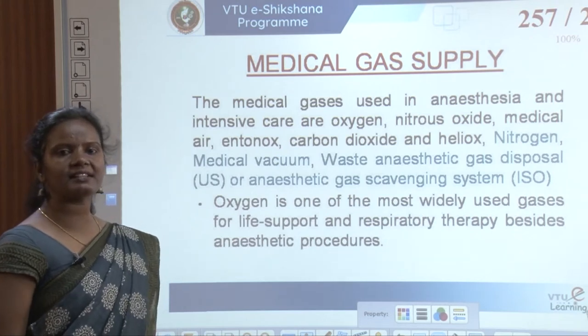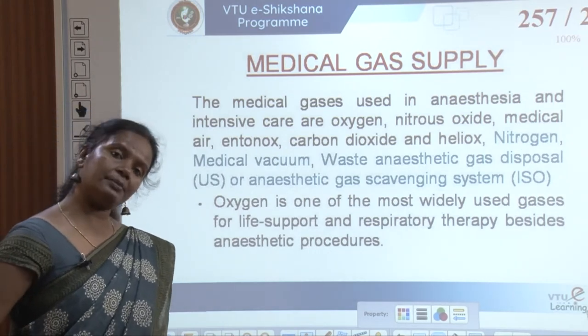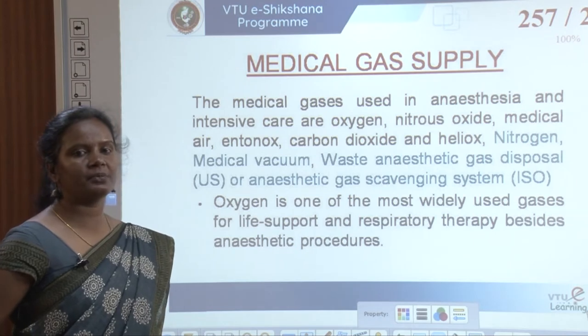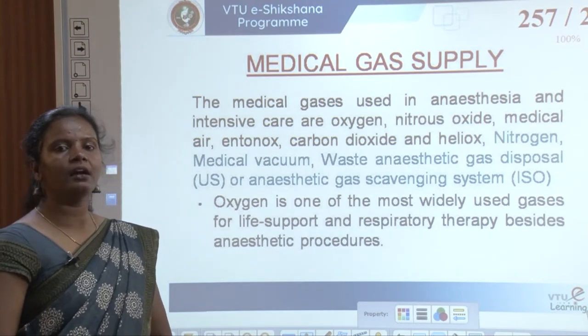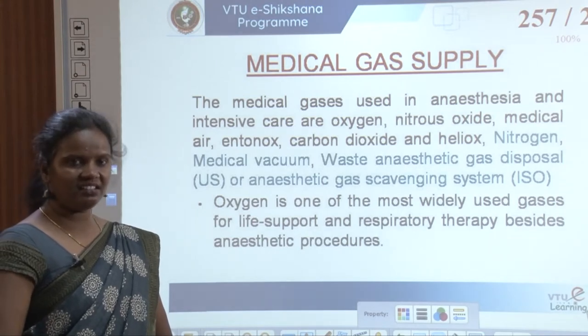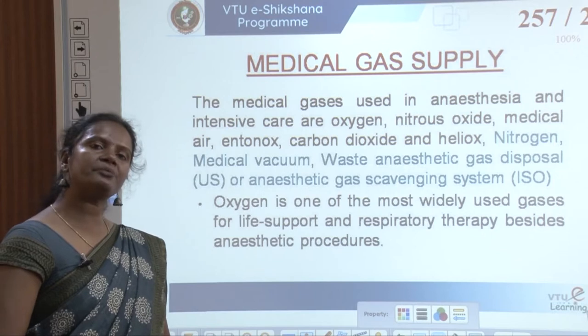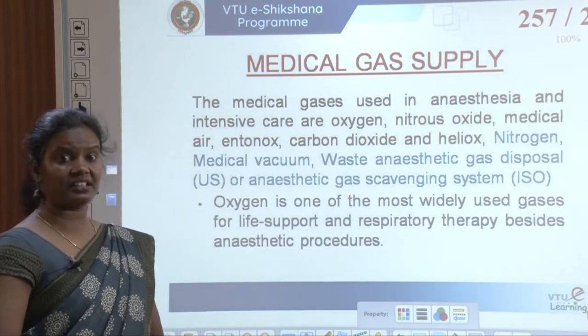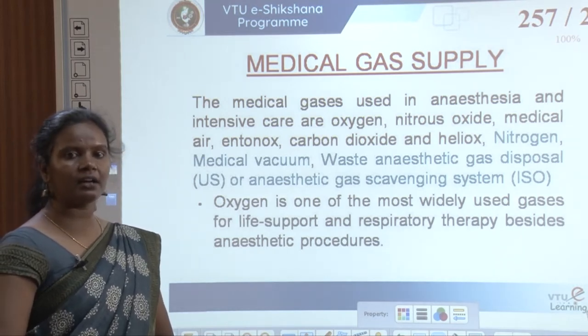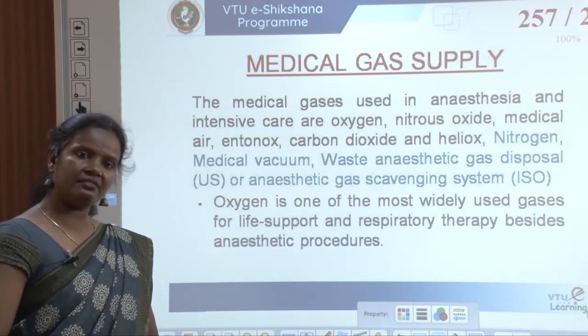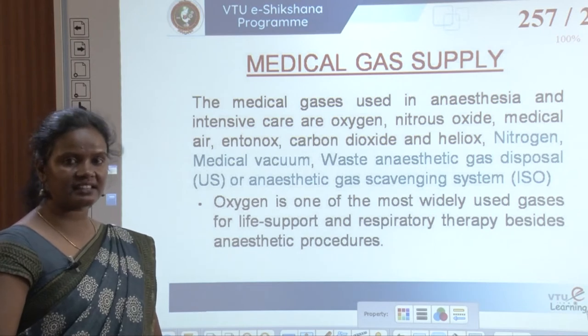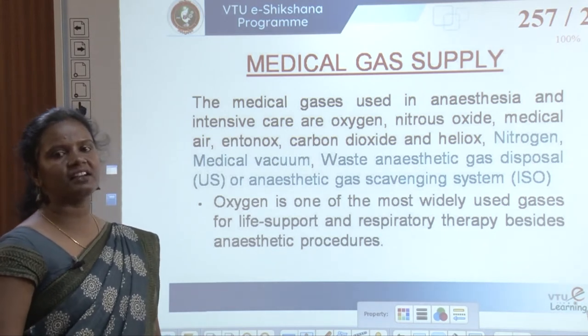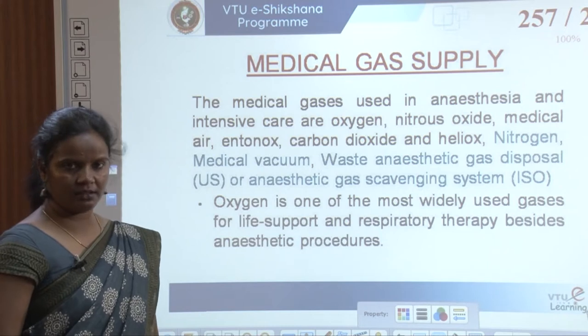The medical gases used in hospitals — particularly in anesthesia, intensive care, and wards — include oxygen, nitrous oxide, medical air, Entonox, carbon dioxide, heliox, nitrogen, medical vacuum, and waste anesthetic gas disposal or anesthetic gas scavenging systems.